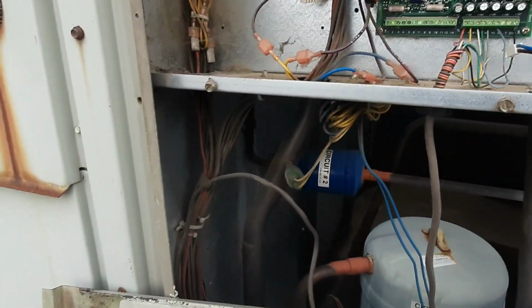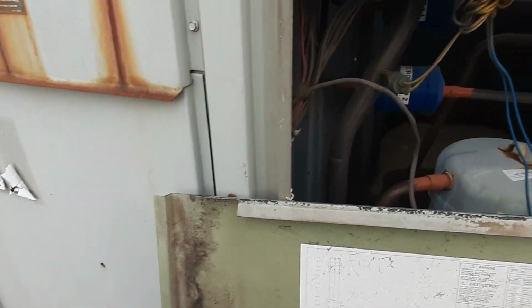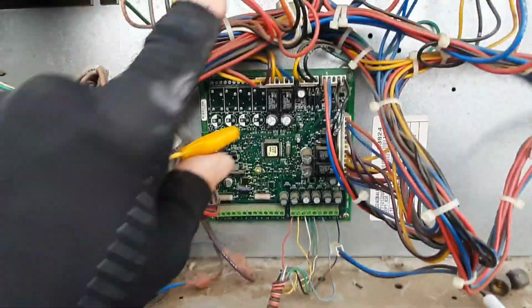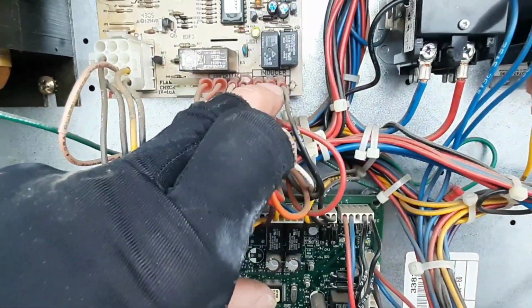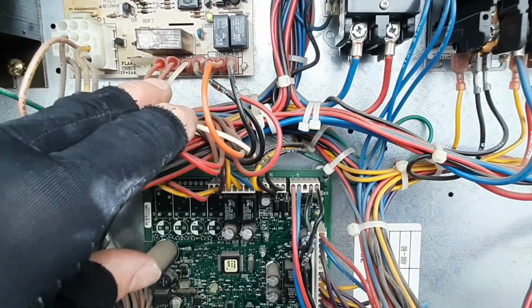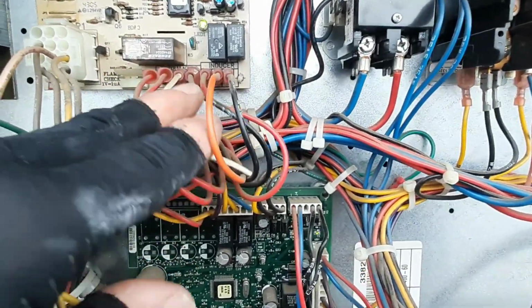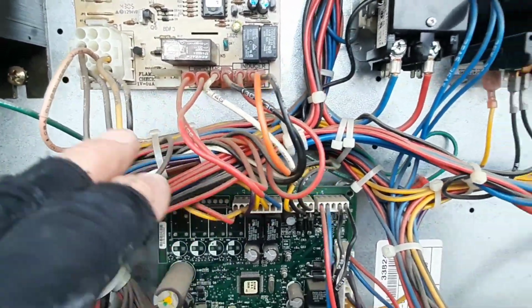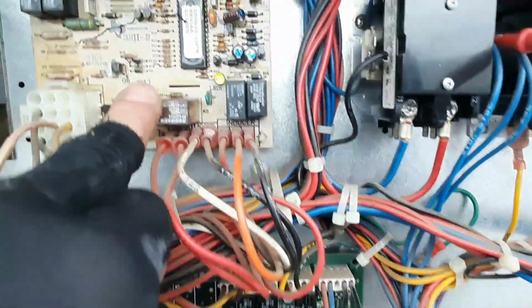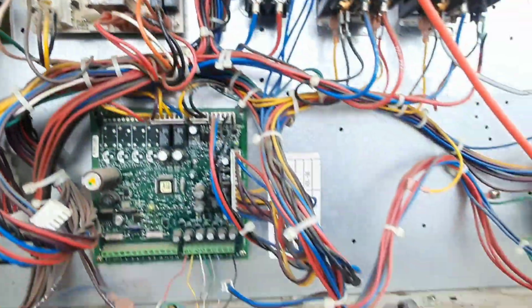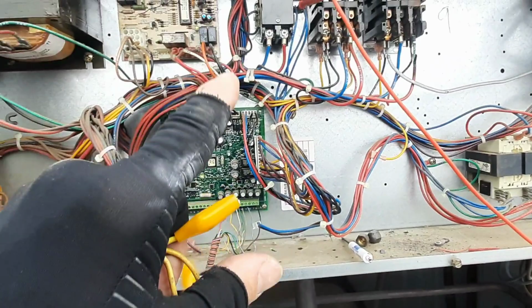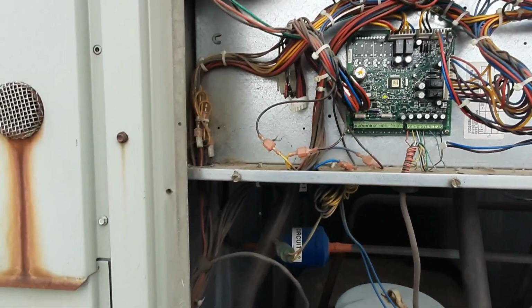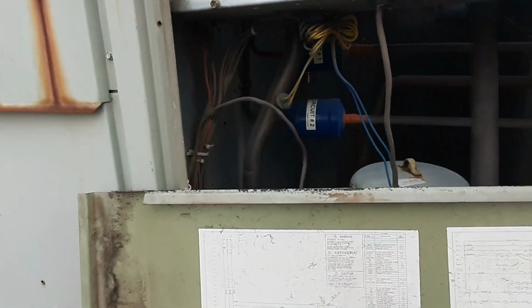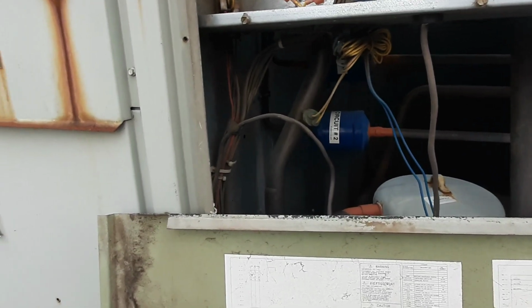So let's pop this. We'll give it a heat call. Let's see if we're getting any voltage coming. So voltage for our inducer should come out there, and then you got power in, and there's your igniter. I mean, the relay. This board's jacked, and they need a new board there. I still can't explain the blower. I'm not sure about that, so it's weird. Let's get over here and see what we got.